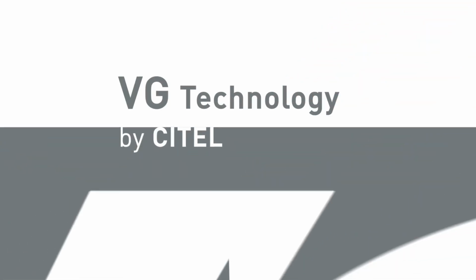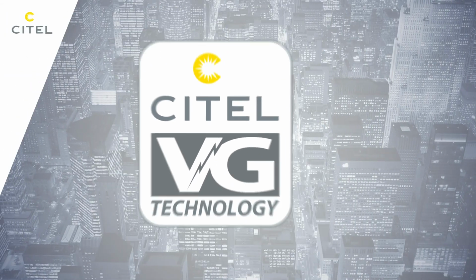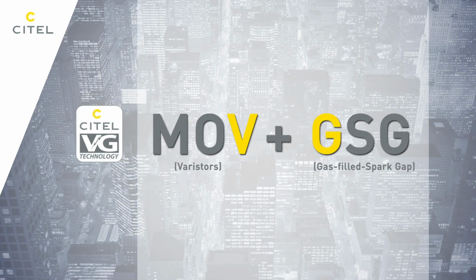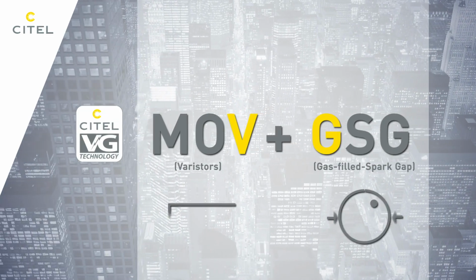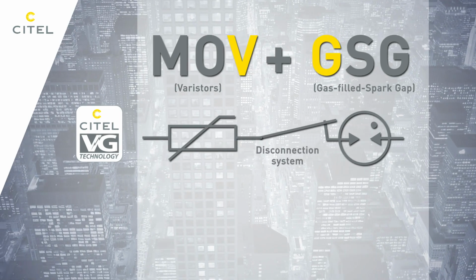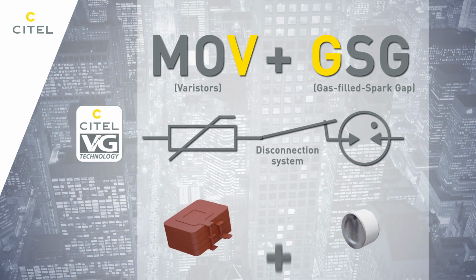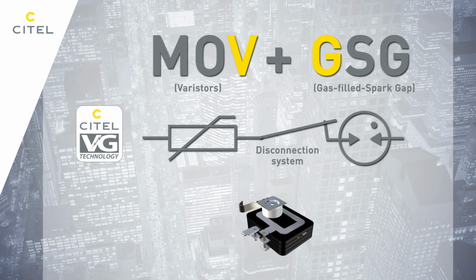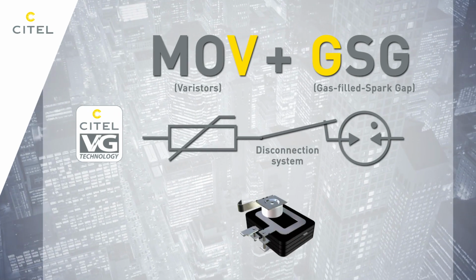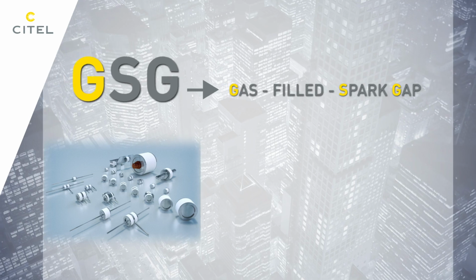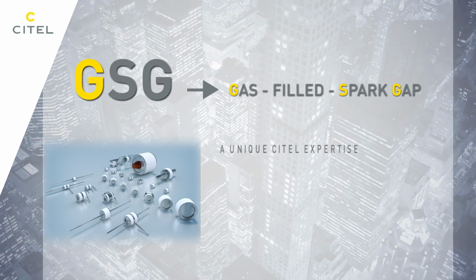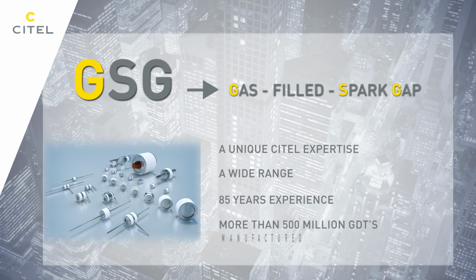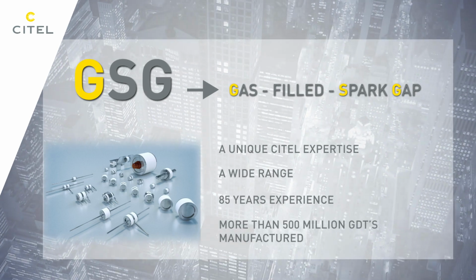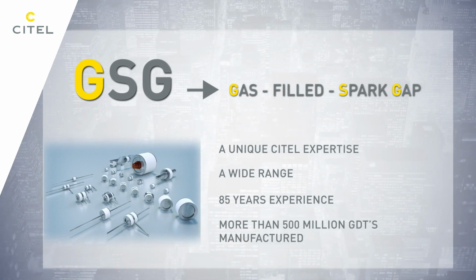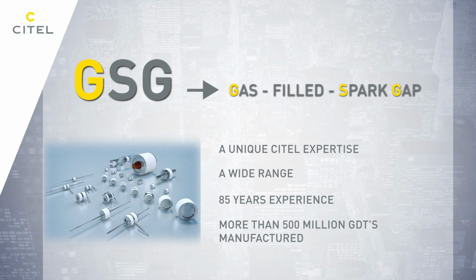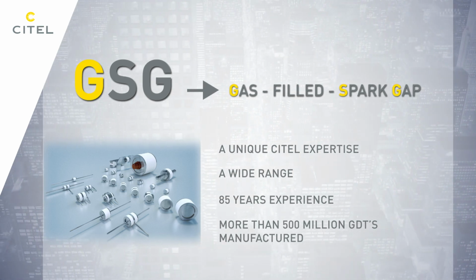CITEL's patented VG technology is the optimized solution for protecting your equipment against transient overvoltages due to lightning or electrical surges. It combines MOV and GSG components to provide a hybrid surge protection device unlike anything else on the market. GSG is a unique CITEL expertise which takes the GDT to the next level. CITEL VG SPDs use specific gas-filled spark gaps and are the result of over 85 years of experience in the industry.